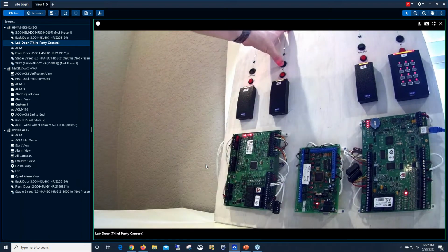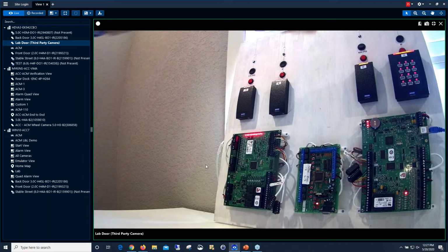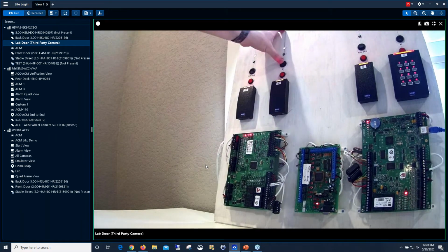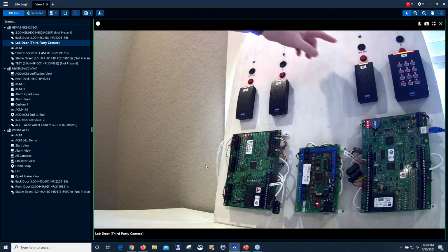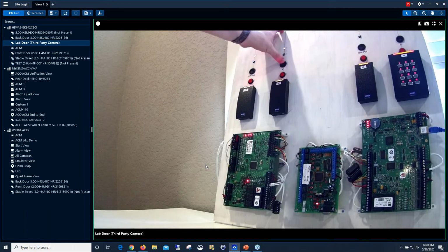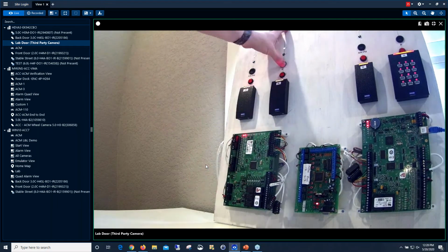So this would probably be a scenario where you have a mag lock on a door because you don't want the door to open if the opposite door is open. So here, again, I'm hitting the REX button, it's not letting me out. So let's go ahead and secure that door contact. Now that this door is closed, let's open up this door. I hit the REX and I'm able to get out the door.